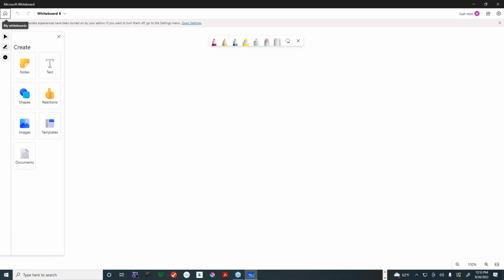Hey, it worked. So if it's an open system, for example, we actually had this a couple of weeks ago. Let me do the most common one, and that's the cooling tower. Let's assume we have a cooling tower in the upper left-hand corner here, and it has a basin, and that basin is where the water is kept. There's a fan at the top in my little oversimplified cooling tower. Then there are a couple of containers or basins at the top, and sometimes these are called the hot deck, and sometimes down here it's called the cold deck.